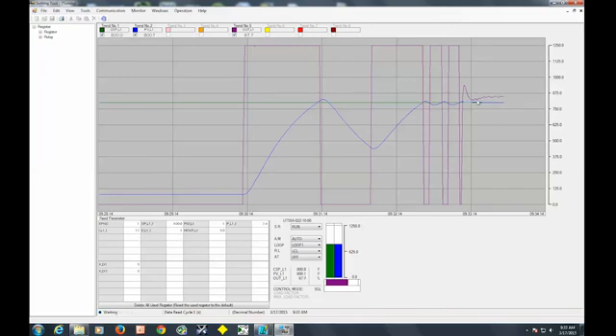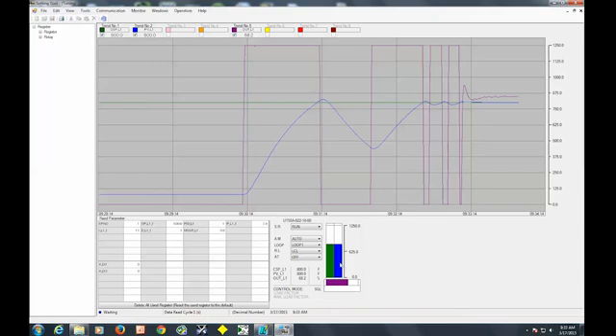So now we can see our outputs modulating slightly. And where we have our set point and process variable that basically appears as one line because we're maintaining that set point now. If we were to change set points now, let's go to the set point parameter. We'll double click and let's change it to some other value, let's say 600 degrees. And you see we'll let the graph shift a bit. We've dropped the set point to 600 here. Our temperature is coming down because our output dropped. And now the output's coming back up slightly to make sure we don't overshoot our set point.